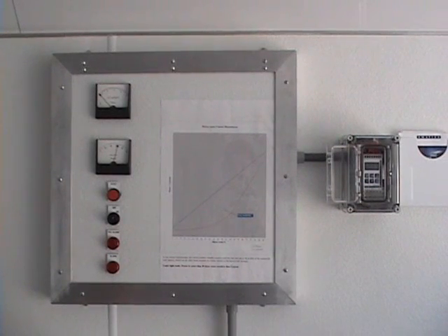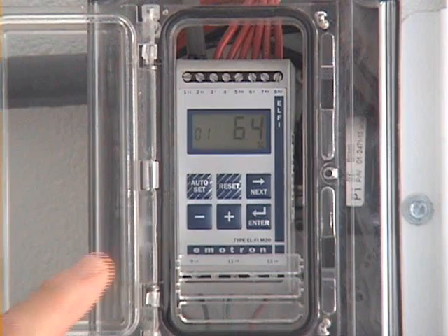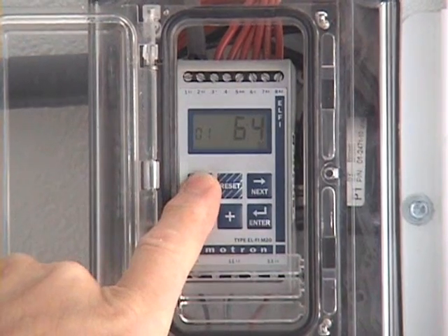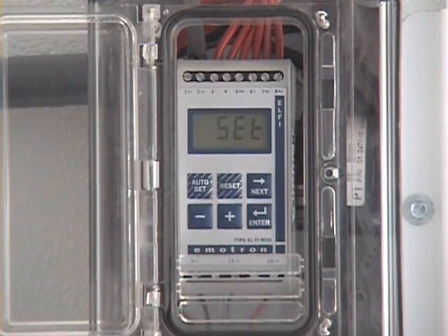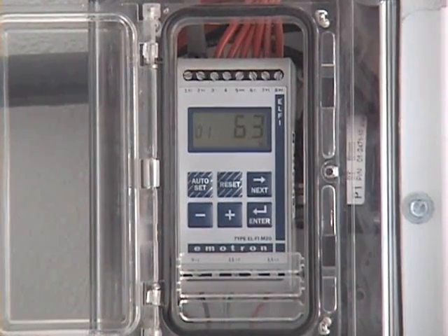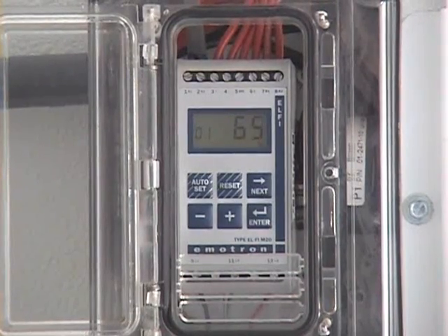Next, we will teach the M20 what the normal load is, and at the same time, establish four levels of protection — two for overload and two for underload. All of this is achieved by simply pressing the auto-set button for three seconds, a unique and patented feature only found on the Emotron load monitor. At the end of the three seconds, the word 'set' appears on the window of the M20. The pump is taking approximately 64% of the motor's rated power to operate under normal conditions.